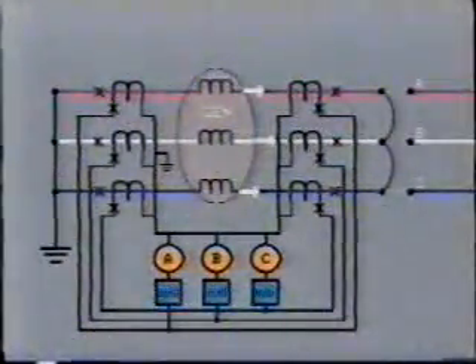The most common way of performing this test, particularly where a new generator is being commissioned, is to place a short circuit across the generator output and run the machine at very low excitation. This allows us to pass load current through the generator windings at low voltage and for a very small amount of power input from the prime mover. This is the established method for drying out the generator winding. It also provides us with an excellent opportunity to check secondary current input to all of the generator protection devices.